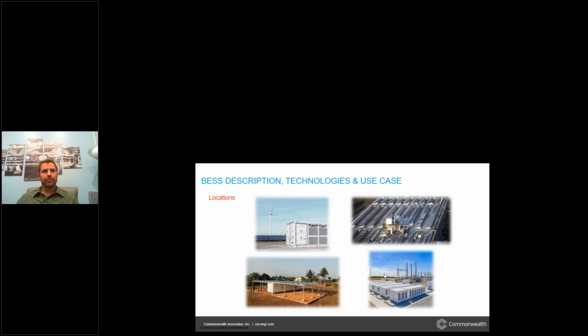This kind of brings me to a new point. Batteries get rated in power and hours, or energy. That's why you see on a DeWalt drill a 5 amp hour battery. That's the rating on that battery. So when the drill draws 5 amps, the battery will run for an hour. It's really no different for a large scale. A 1 megawatt hour battery can dispatch 1 megawatt for 1 hour. So with a rating of 5 megawatt, 10 megawatt hour, the system can dispatch 5 megawatts for 2 hours. There are also beginning of life ratings and end of life ratings, like your cell phone. When a battery's brand new, it's awesome, but over time you start having to recharge over the course of the day, when previously you may have gotten through the whole day. And then there's also the battery's round trip efficiency, state of charge, charge rate, and they go on.